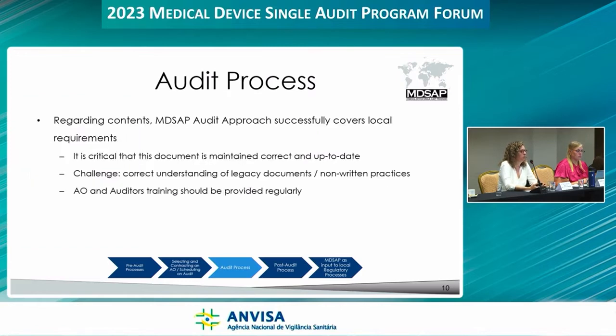Regarding the contents of the MDSAP audit approach document, we understand that it successfully covers local requirements, but we want to highlight the criticality of the document being correct and up to date, as well as training being provided to the auditing organization and to the auditors. These messages need to be conveyed to the front line, because some of the requirements date from before the program. So they were written in the context of a local market and not to explain to foreign markets how to implement this specific requirement.